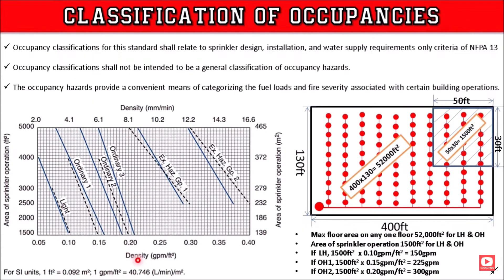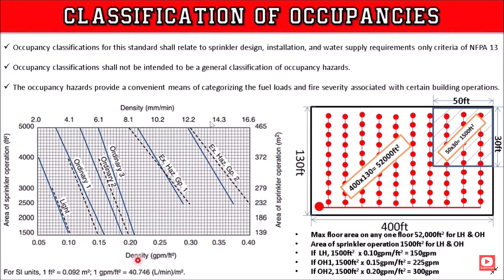We are going to look at the density of water flow. The density is set up on the page, and the area of sprinkler operation is multiplied by the density of water flow. The area of sprinkler operation is then used to calculate the required water flow as per NFPA 13.